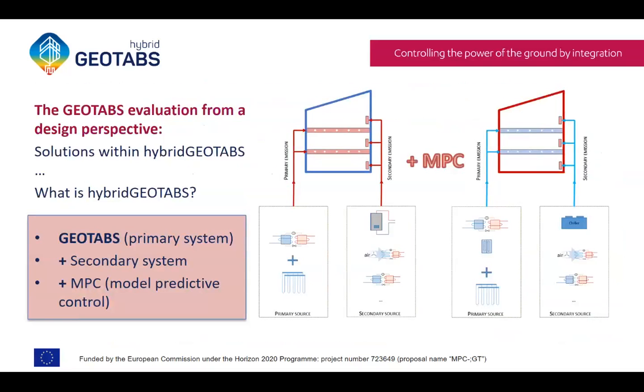Good, let's look further. How do we solve this problem? As explained already, we have a hybrid GEOTABS, and hybrid GEOTABS consists of 3 elements. One element is the GEOTABS, which we know already. Then we have the secondary emission system and the secondary supply system, together called the secondary system. It should be faster, it should be cheaper, and if it's less environmentally friendly, that's okay, as long as we put the largest share of energy use on the primary system, being the GEOTABS. So it's really a kind of helping system that should only work when it's really needed.